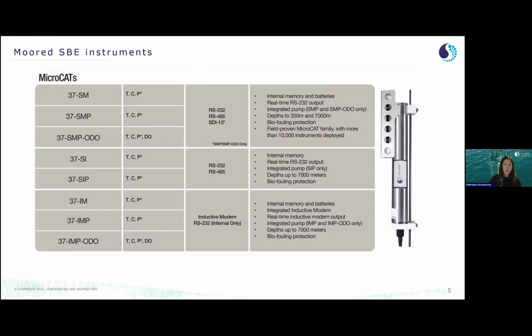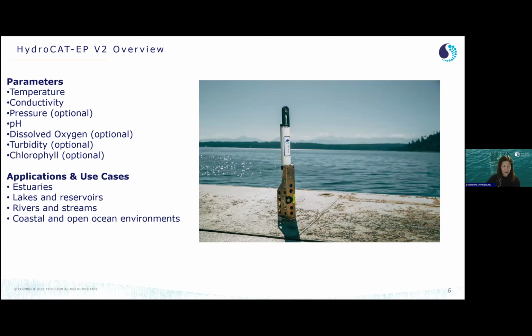The HydroCAT-EP V2 was in a way born from this line of sensors, the 37, and is a very powerful multiparametric CTD. I like to call it the Swiss Army knife, as you can measure a number of different parameters with only one instrument. It has, of course, a temperature and conductivity sensor, like all Seabird CTDs. It also has an optional pressure sensor, dissolved oxygen, turbidity, and chlorophyll. What is particularly unique about the HydroCAT-EP V2 is that it has an integrated field-swappable pH sensor that was specially designed for it.